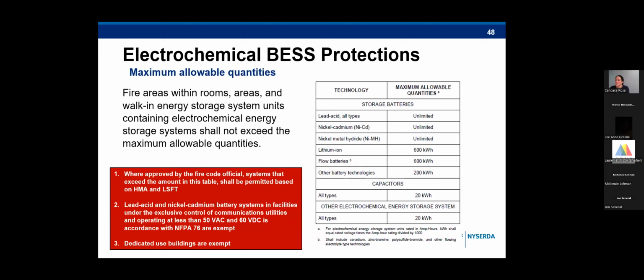So this slide represents the maximum allowable quantities that were discussed earlier in the presentation. If an installer wants to exceed the values in this table, they will need to conduct the hazard mitigation analysis and large-scale fire testing to show that the system will be safe.